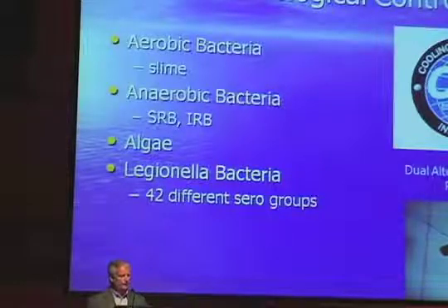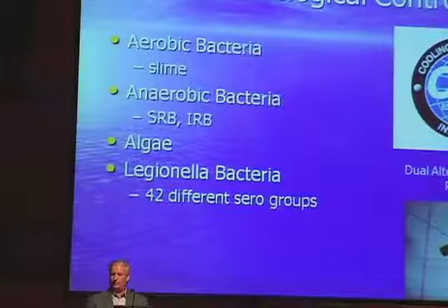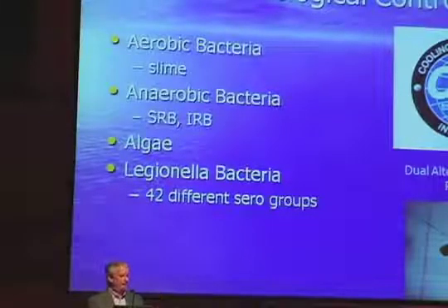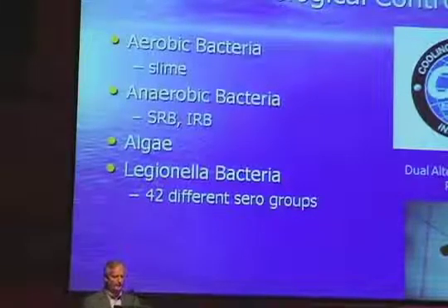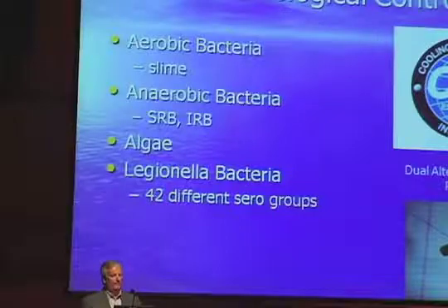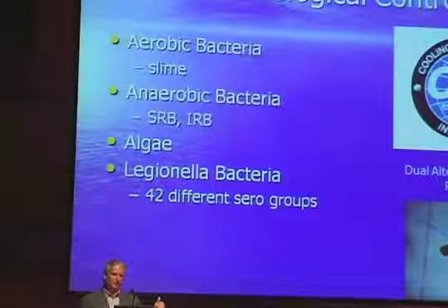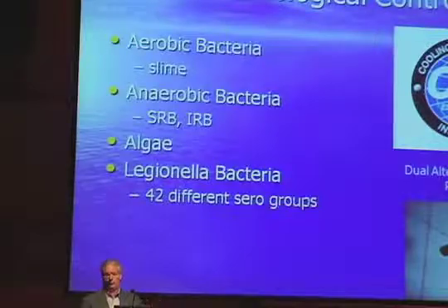And then, of course, we've got algae. Now, we don't see algae in condensers because there's no sunlight. The only place we see algae is where there's sunlight. So if you can find a way to enclose your cooling tower where there's no sunlight, life is good. You won't see algae. And then, of course, there's Legionella, and we'll talk about that a little later. What we normally find around the country is that if you control your aerobic bacteria with the normal performance standards, we normally don't see issues with Legionella. Now, that might vary a little bit with healthcare. We'll talk about that later.